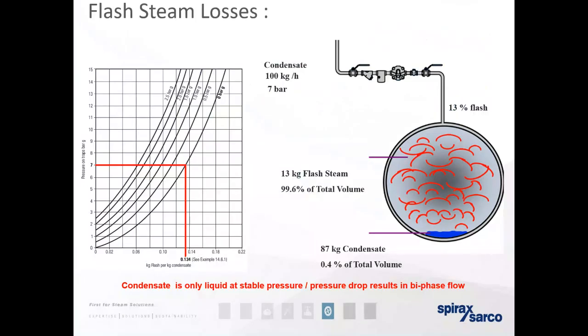So flash steam losses. As you can see here, we have an example of a condensate pipe. The condensate pipe here in this particular case is 100 kilograms an hour at 7 bar, which means it has about 13% flash steam, which accounts for 99.6% of the volume. 87 kilograms of condensate only counts for 0.4% of the total volume in your pipe. So the reason we show this example is we think of condensate being a liquid. It's mostly steam, and that's losses that you see coming down from the differential pressure. So the changing of pressure from your steam system to condensate line, flashing off, causing flash steam in your pipe. We refer to this as a biphase flow, which just means it's steam and condensate in that line.